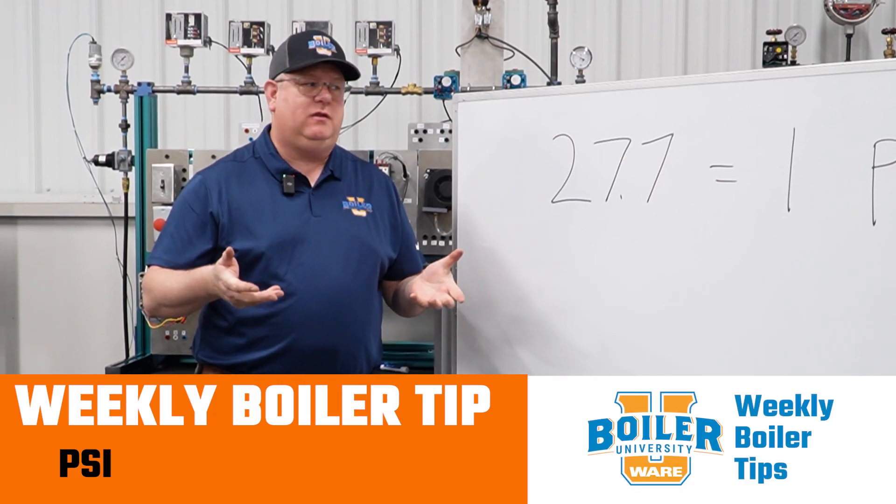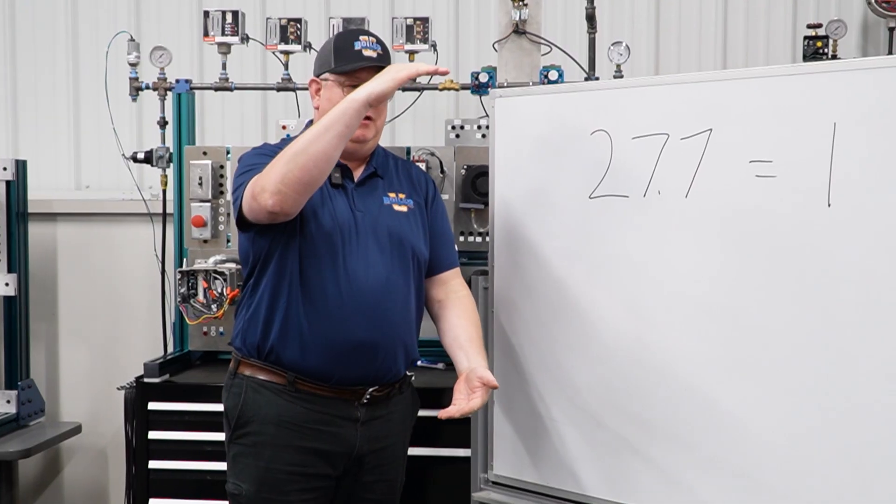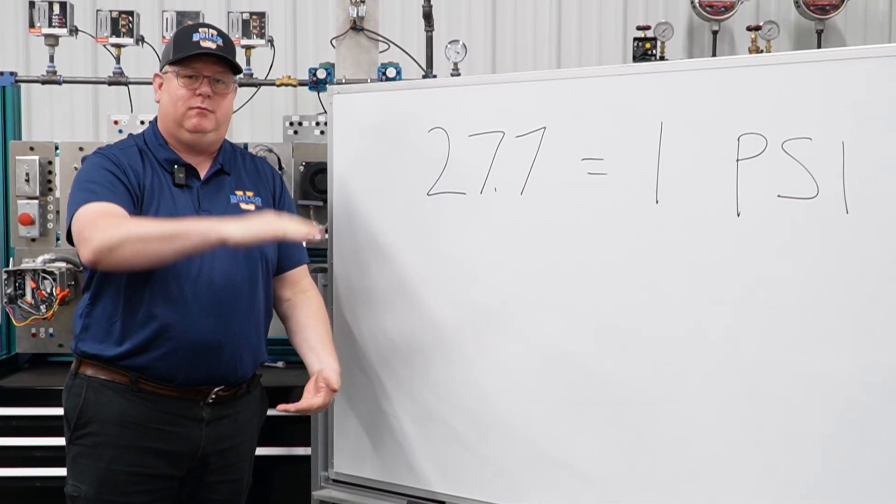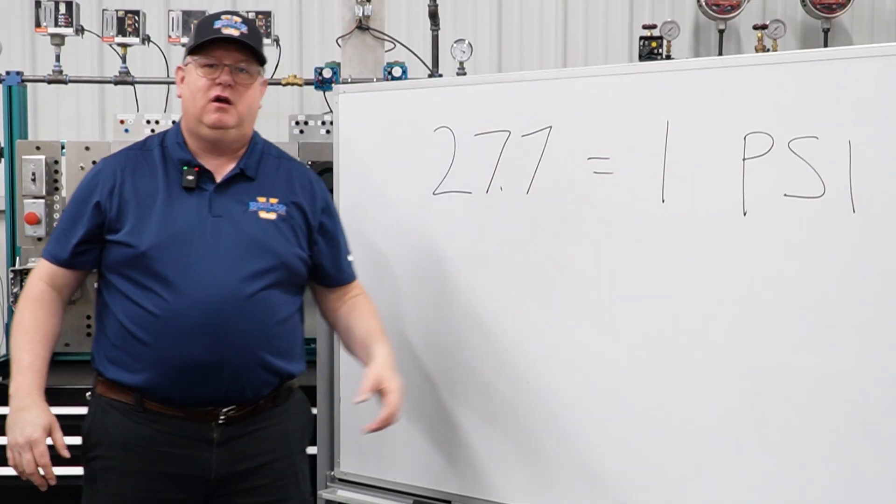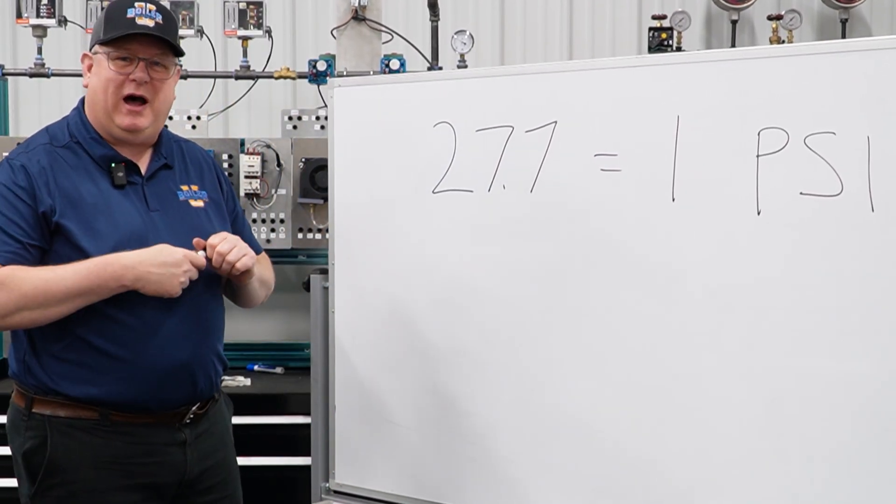The question that we got recently was, if 27.7 or roughly 28 inches of water column equals 1 PSI, doesn't it make a difference what size the pipe is?